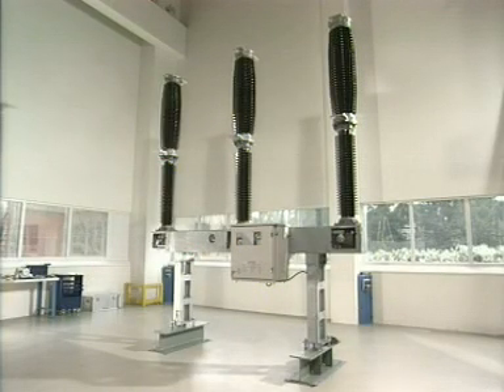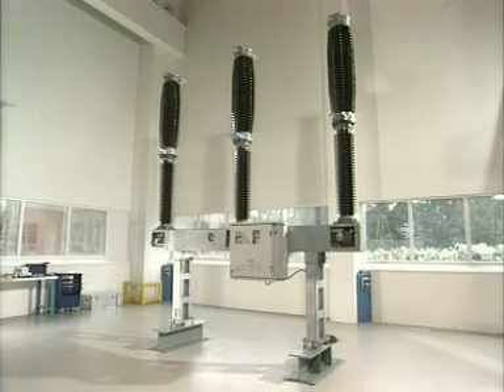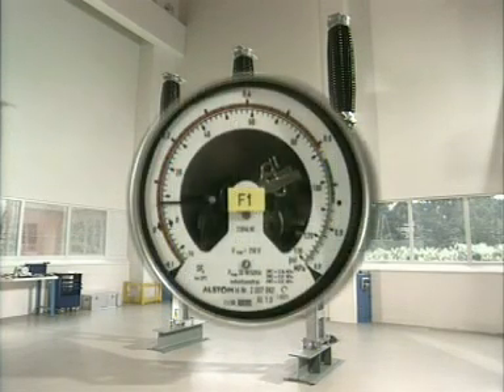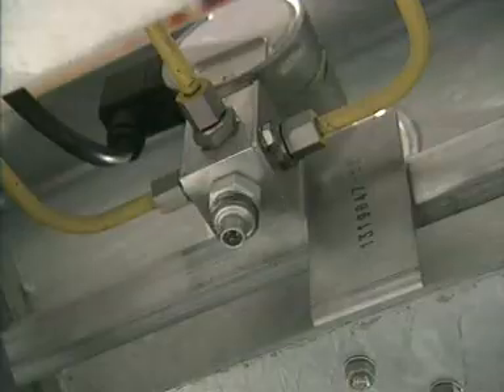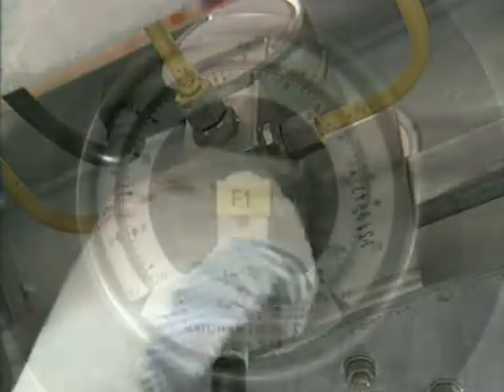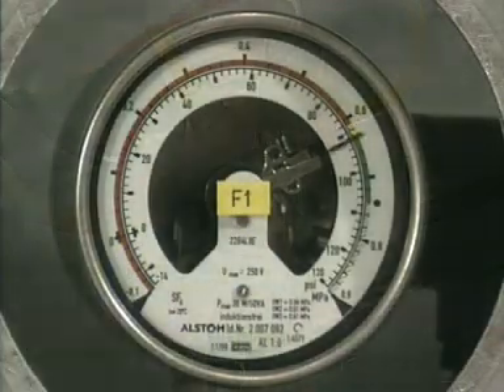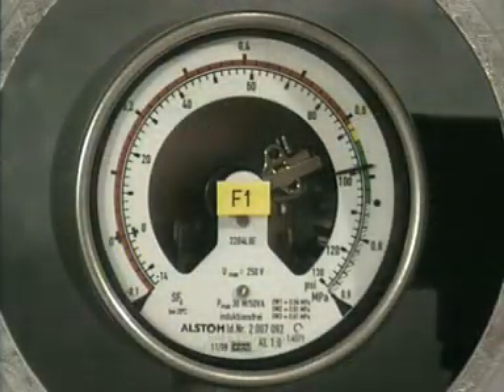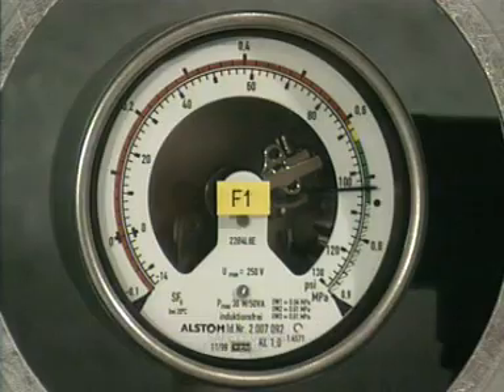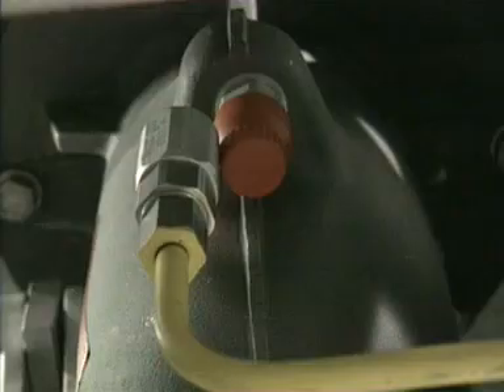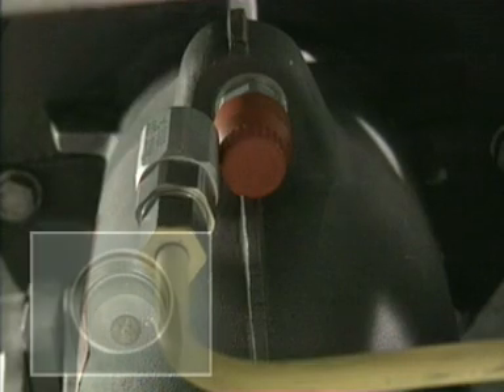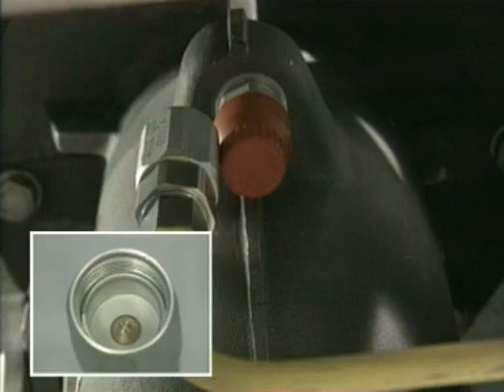The recommissioning procedure for the circuit breaker GL311 or GL312 begins with the testing of the density monitor. Connect the gas filling device to the central supply connection and fill the piping system and density monitor with SF6 gas up to the rated pressure given on the nameplate. Since the ends of the piping system are equipped with check valves, uncontrolled leaks of SF6 are prevented.